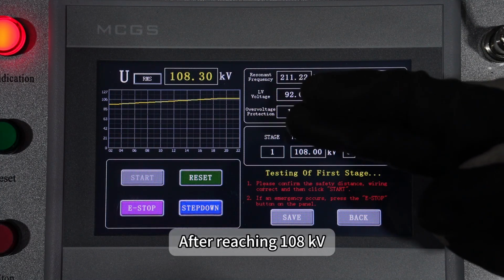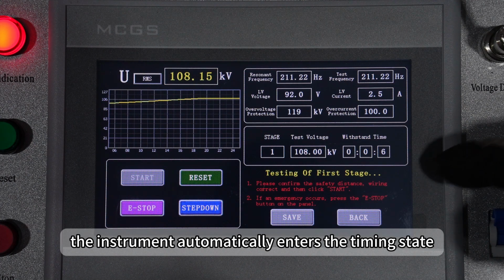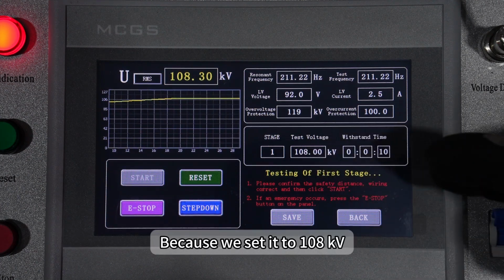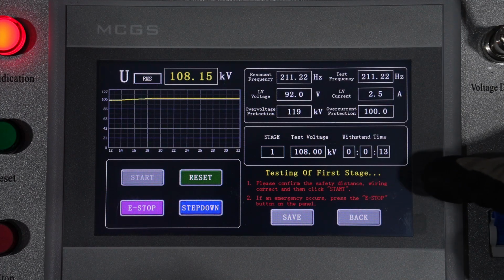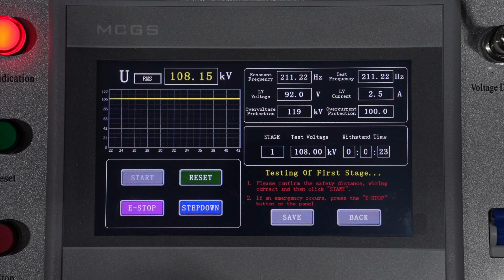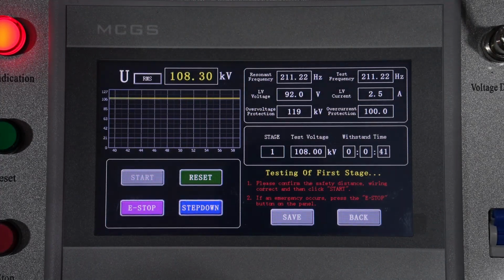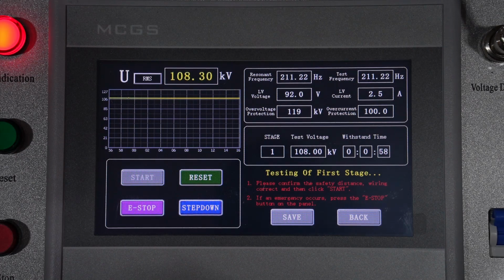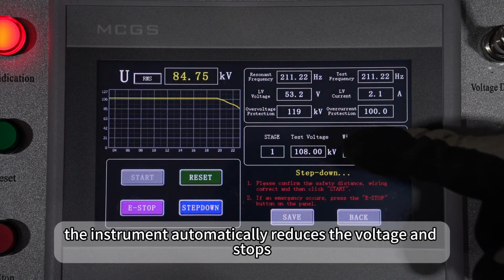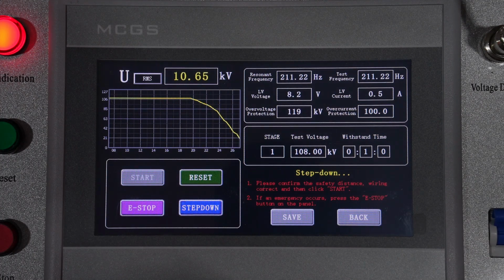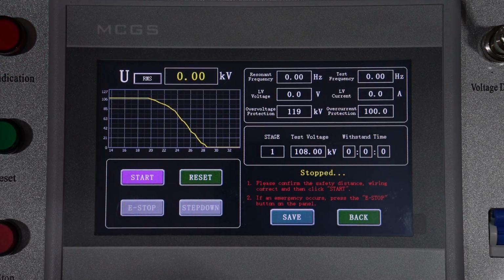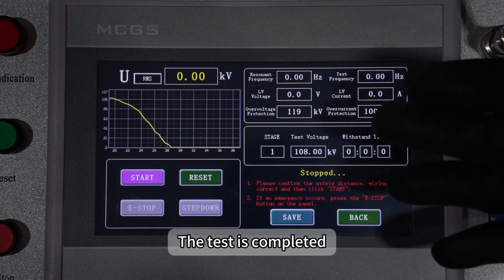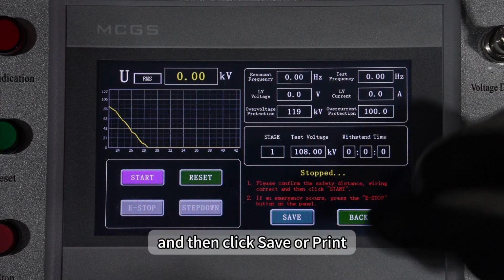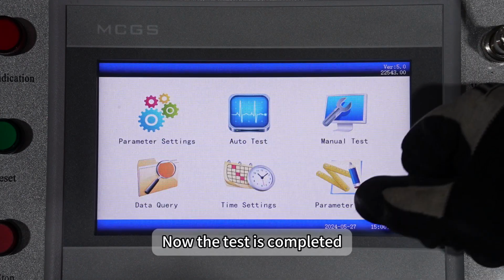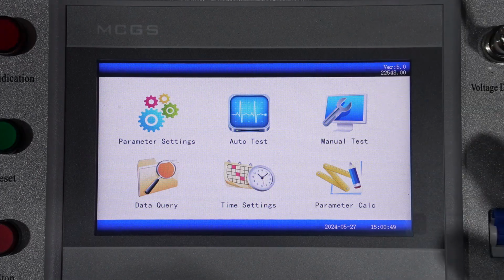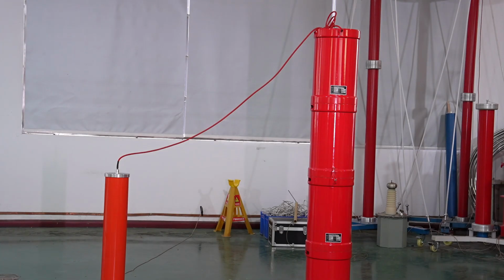After reaching 108 kV, the instrument automatically enters the timing state. Because we set it to 108 kV, 1 minute. After 1 minute, the instrument automatically reduces the voltage and stops. The test is completed. We can choose to confirm, and then click Save or Print. Now the test is completed. Return. Turn off the power. And finally discharge.